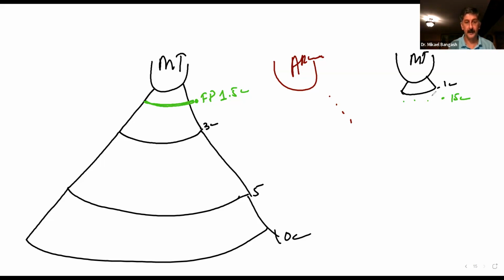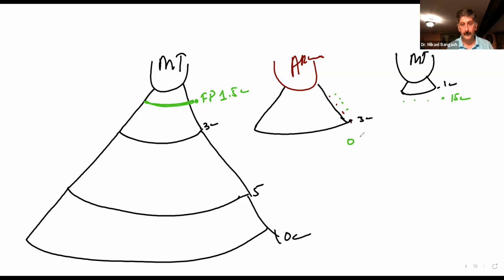Okay, so say we had an annular array transducer, and we have kept the imaging depth at 3 centimeters. The limitation here is that you will not be able to focus your beam beyond 3 centimeters, because the total depth that you're imaging to is 3 centimeters. So you can't really say, well, I want to focus at a depth of, let's say, 4 centimeters, because you're not really scanning that area of 4 centimeters.